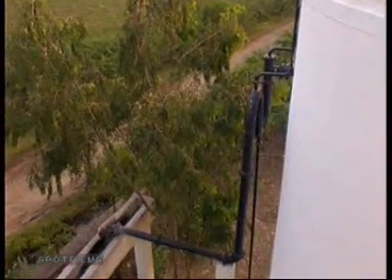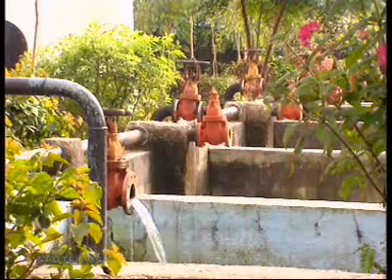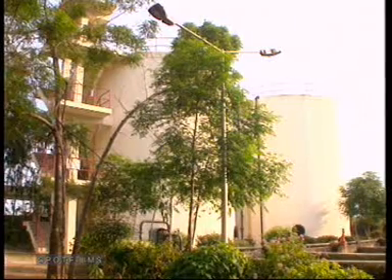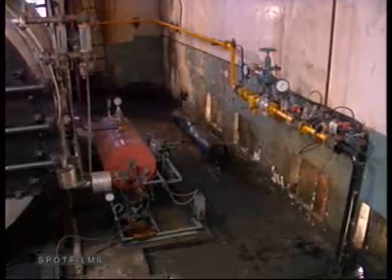The anaerobic and aerobic treatment turns the effluent into clear, safe water, which waters the garden and feeds the fish ponds. It also generates 30 cubic meters of biogas every day, replacing about 75 liters of oil in this unit, which also saves over 150,000 rupees every year.